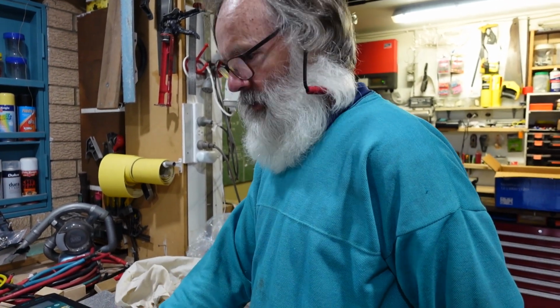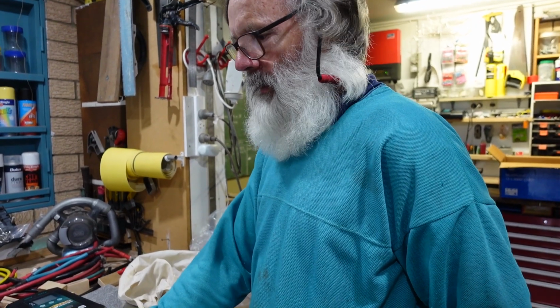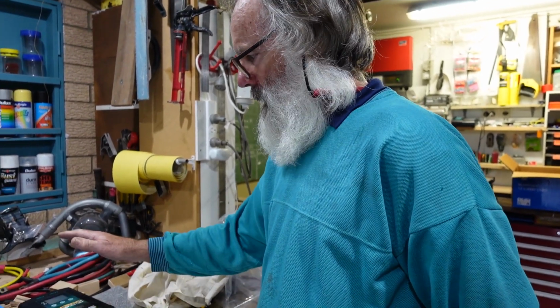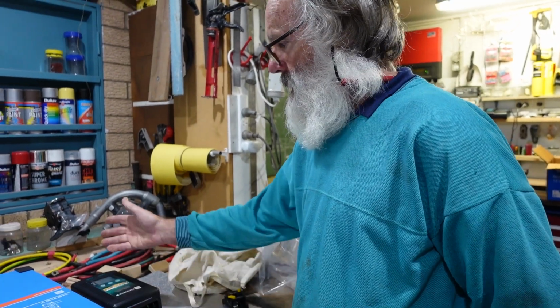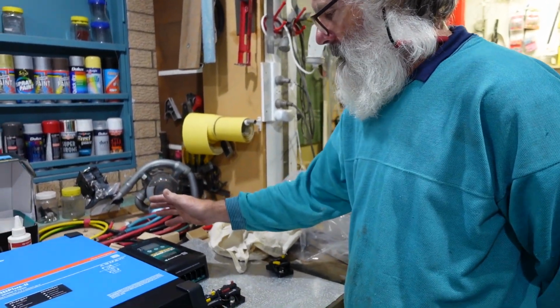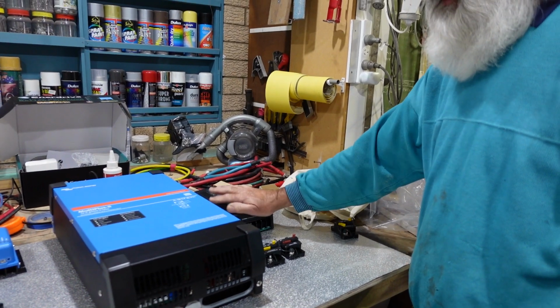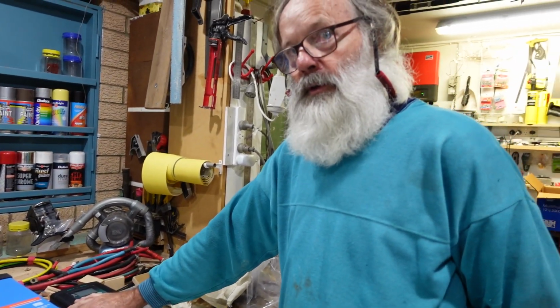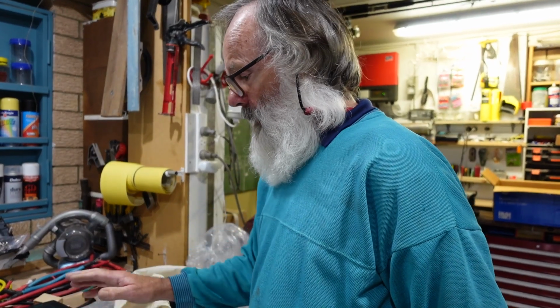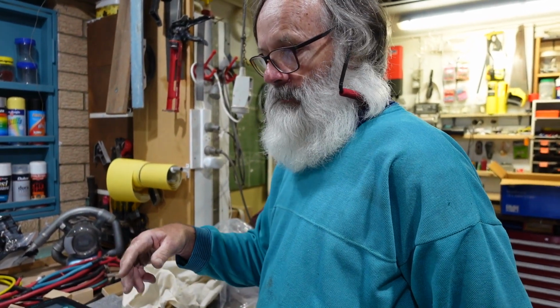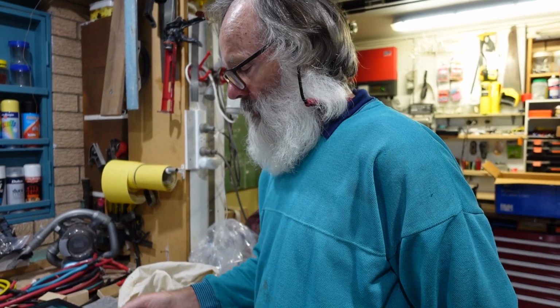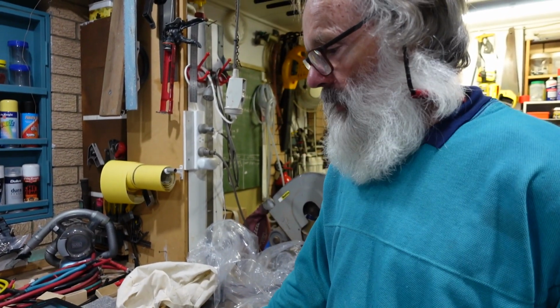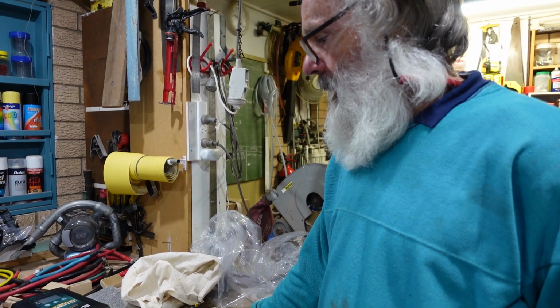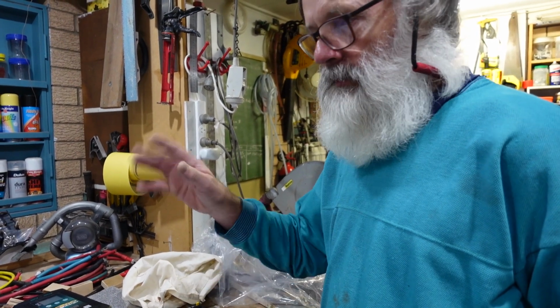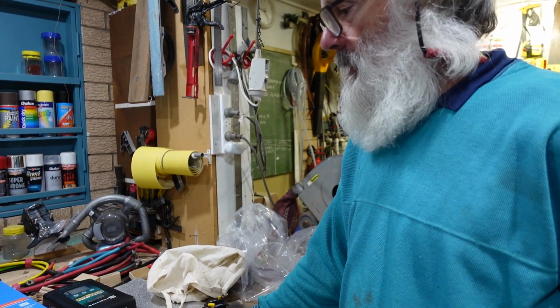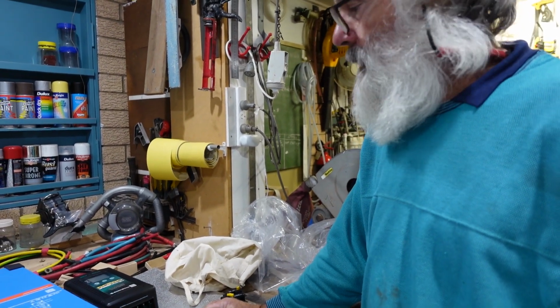Put your circuit breaker in according to your wire gauge, not the item at the end of it. Like in this case, we've got a 50 amp capable DC to DC charger, but we're only going to be running 15 amps through it because of our small alternators. But our wire gauge will be capable of carrying probably 80 to 100 amps, because we'll probably use 10 mil squared or 16 mil squared. So our circuit breakers can be quite low, we really don't have to be protecting 100 amp wires.